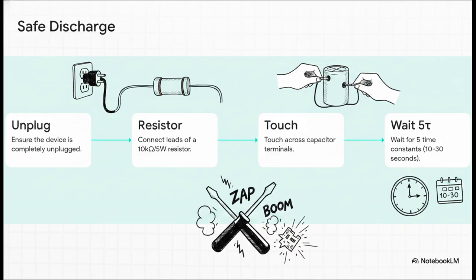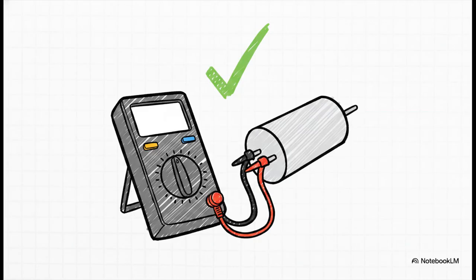Never, ever use a screwdriver to just short the terminals together. A direct short will create a massive arc flash. It could potentially weld your tool to the terminals, and it will instantly blow the copper traces right off the printed circuit board. So the crucial takeaway here is, checking with the multimeter is your absolute final rite of passage before safely touching any internal circuitry. Set your digital multimeter to DC voltage. Place the probes right across the capacitor terminals. You are looking for a reading of less than 1 volt. Once you see that 0 point something, you are finally safe to begin your internal diagnostics.